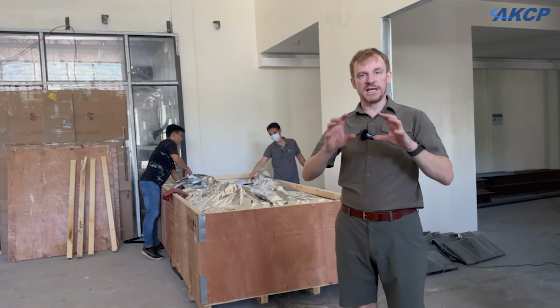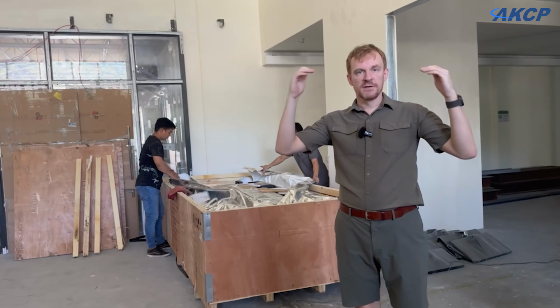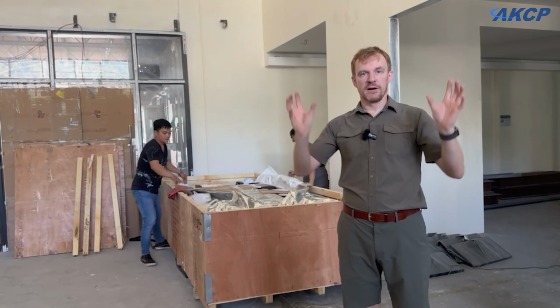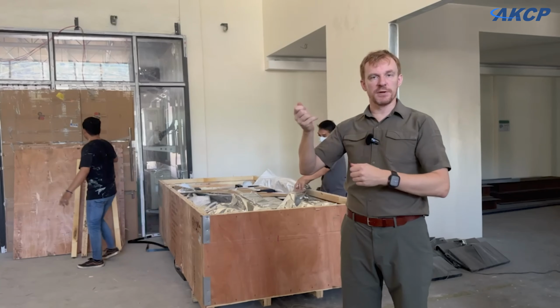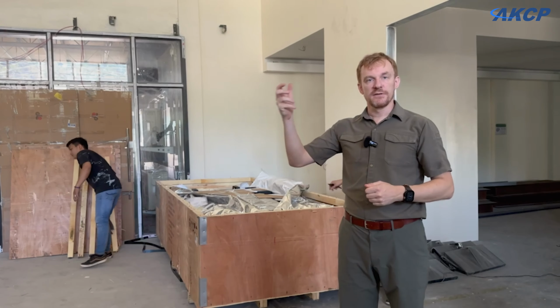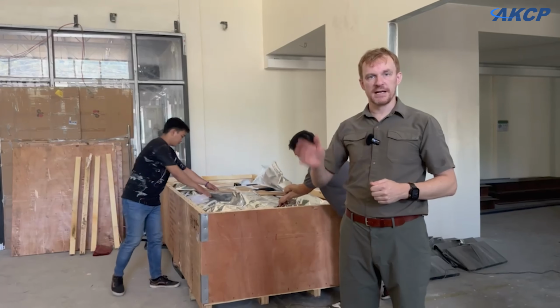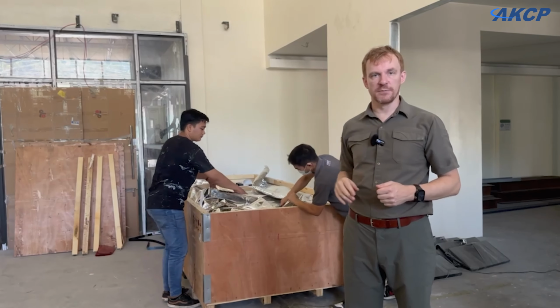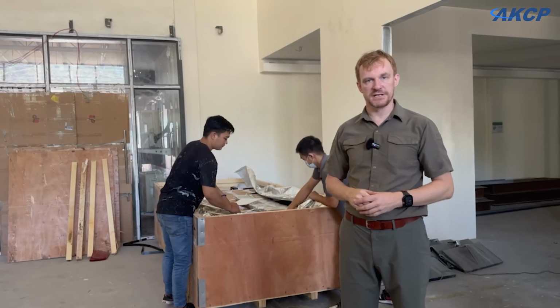These are effectively extruded aluminum channels hung from the ceiling. Onto those we have breakout boxes with plugs and connectors that connect to each individual rack, and inside there's power metering and breakers so we can do PUE calculations and so on.